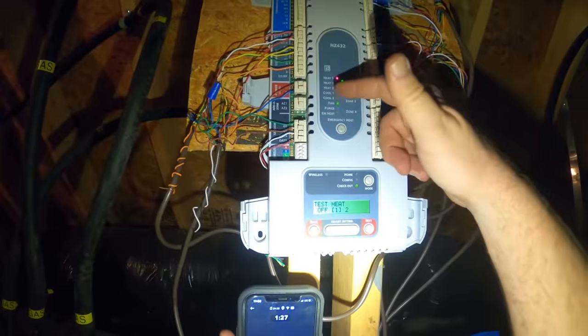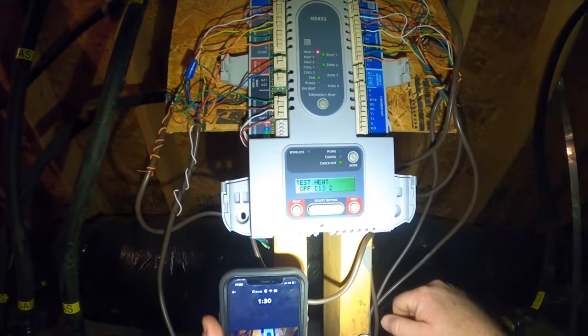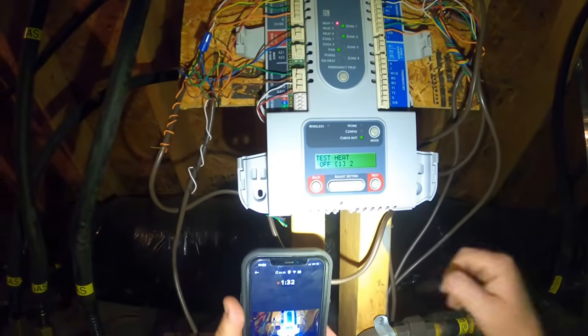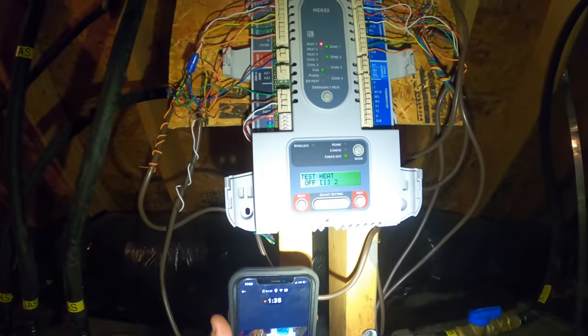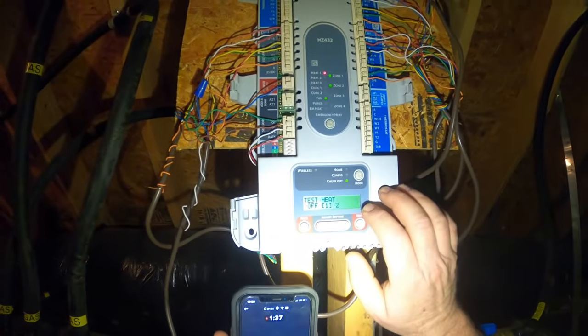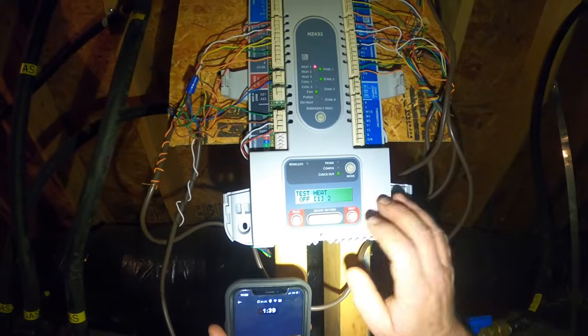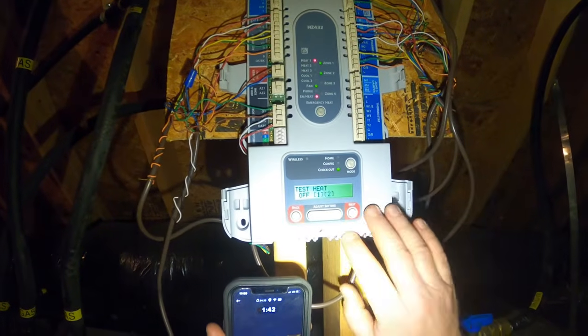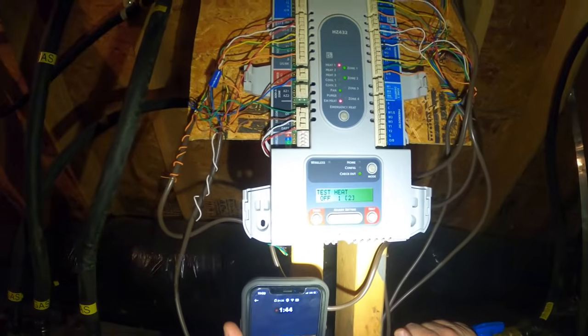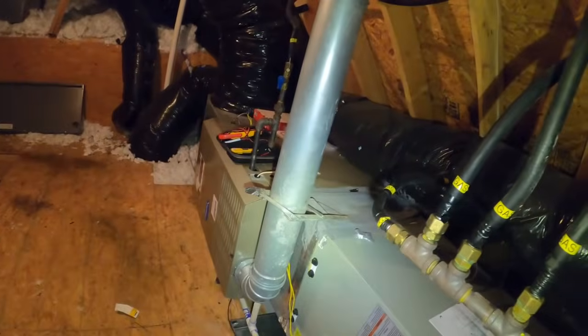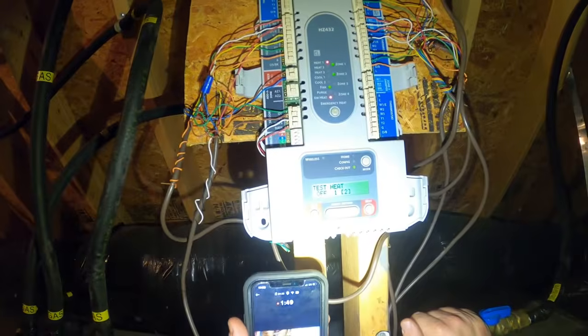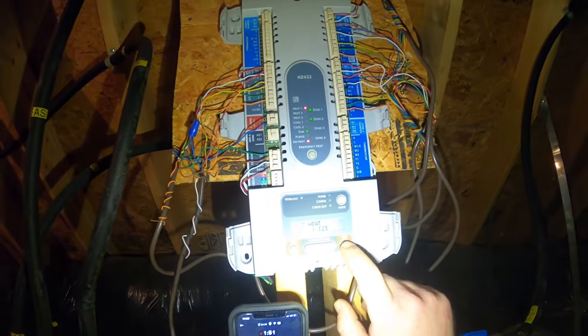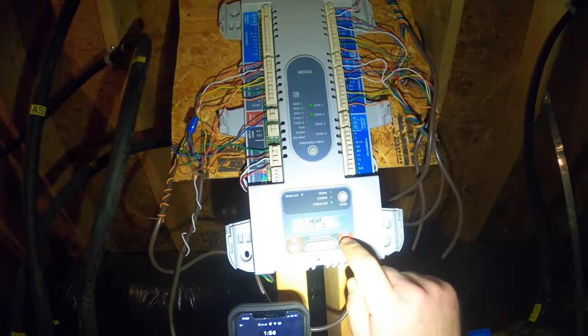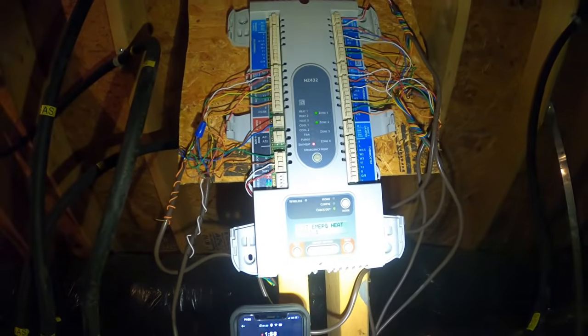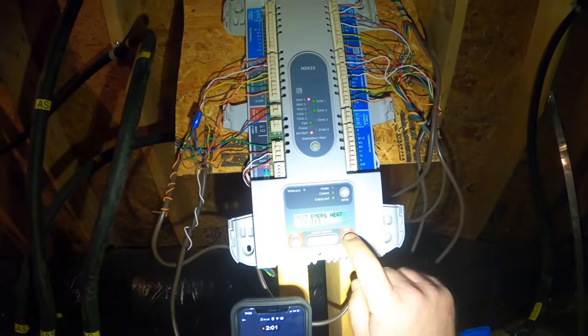Blower comes on. It's going to cycle the outdoor unit in heating. I have the disconnect out there. But now we're going to go to our second heat stage, which is going to be our gas auxiliary. Alright, we hear the furnace. We hear the inducer motor coming on. Furnace will fire off. So we're going to go back to the off mode. Now we're going to test the emergency heat.